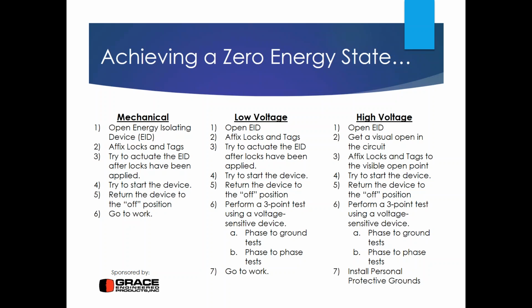So this is sometimes known as known, unknown, known, live, dead, live, and dead is a misnomer there. You're not dead until you do that 3rd check. But that's the 3-point test is the only difference between mechanical and low voltage lockout.